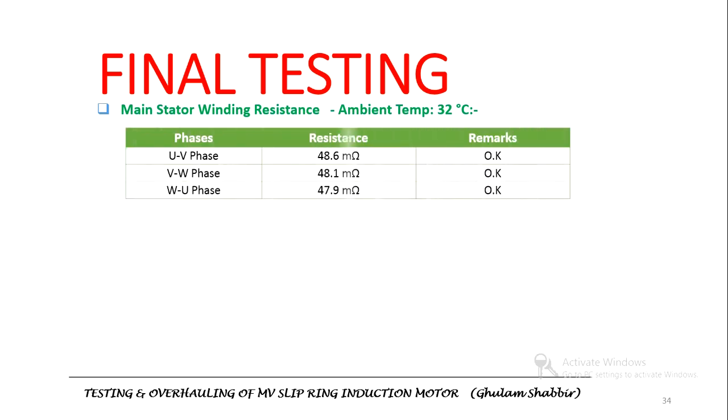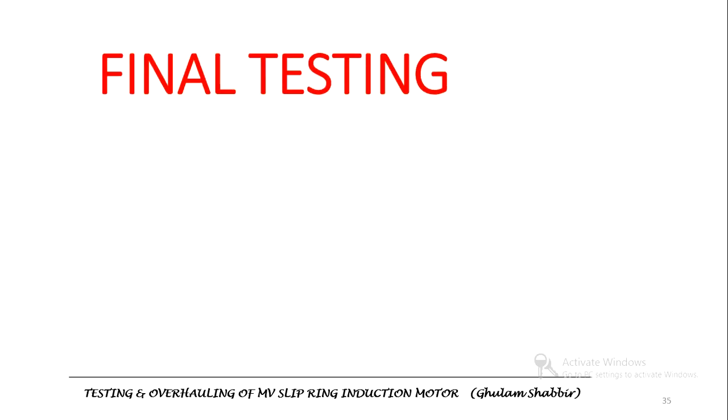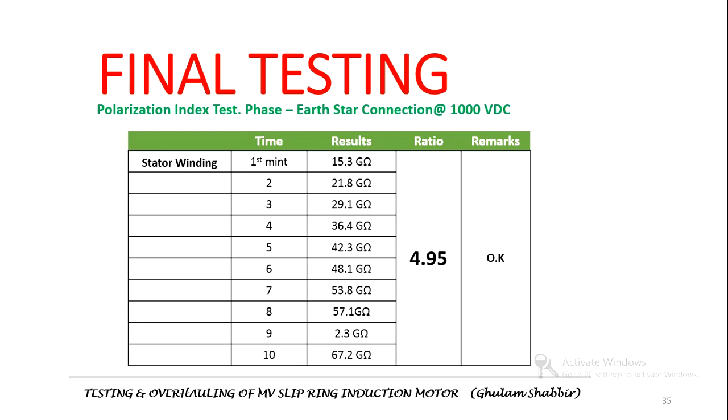Winding resistance for the stator and rotor was also measured again. We also measured the polarization index for the stator. The polarization index, or PI, is the ratio of insulation resistance after 10 minutes divided by insulation resistance after 1 minute. This test is conducted to determine contaminants and physical changes in motor insulation. The PI value recorded was 4.95, which means the insulation condition is acceptable.